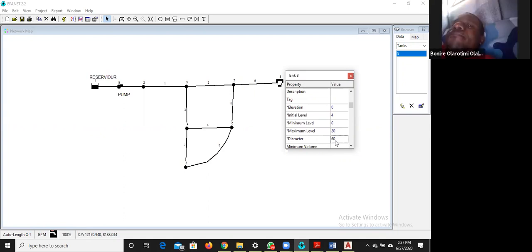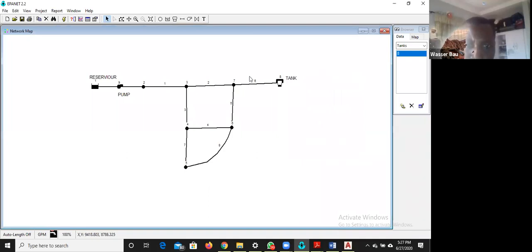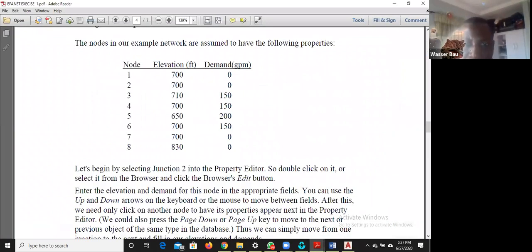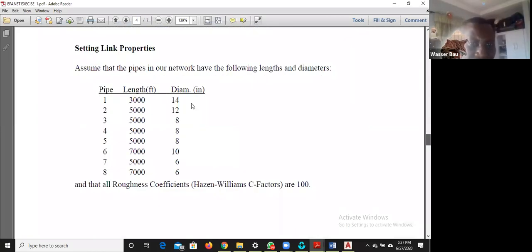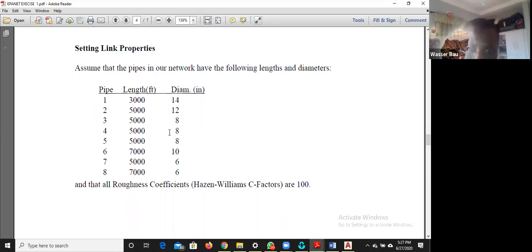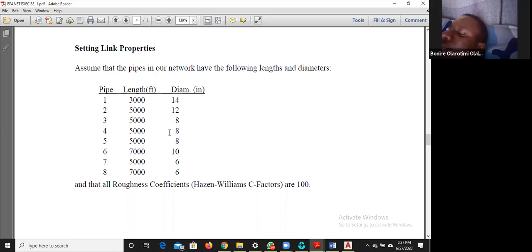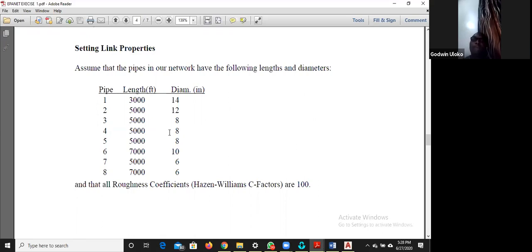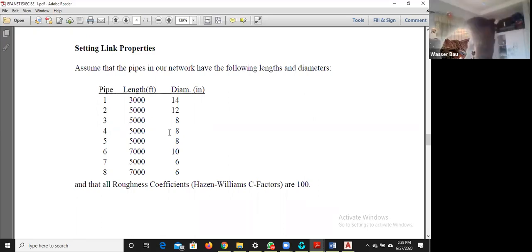We have now entered the node properties. The next step is to enter the link properties — these are the remaining two of the four required parameters. Your job as an engineer is to determine those four parameters. You must first get your demand, then use charts like the Hazen-Williams chart, Manning chart, Colebrook chart, or others to determine your pipe sizes.